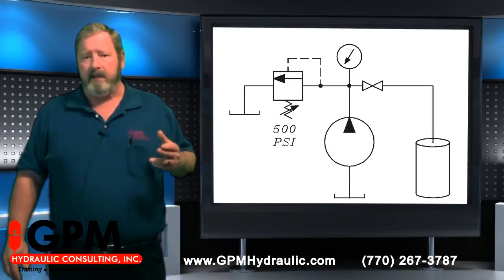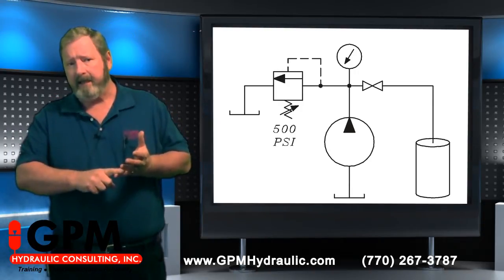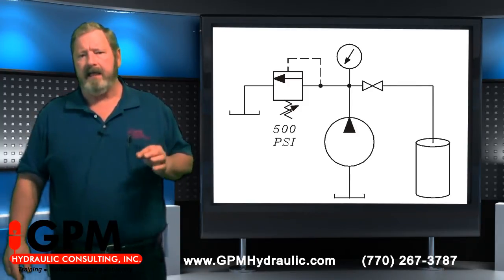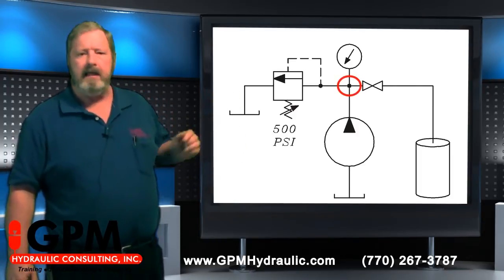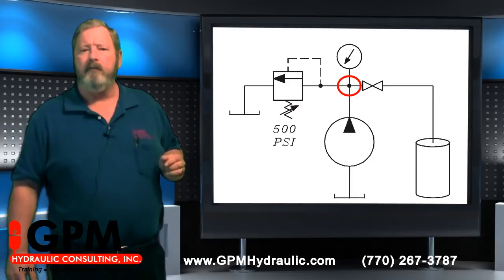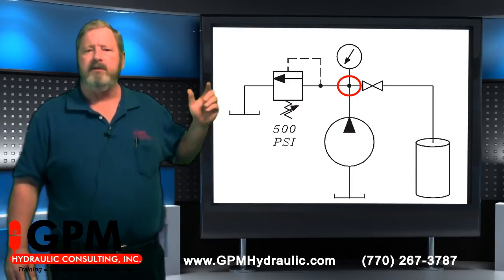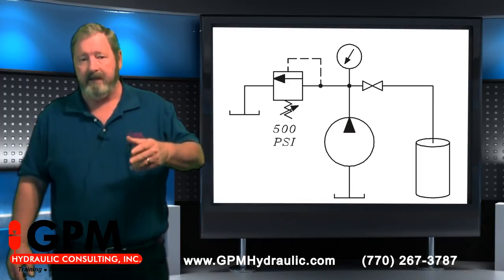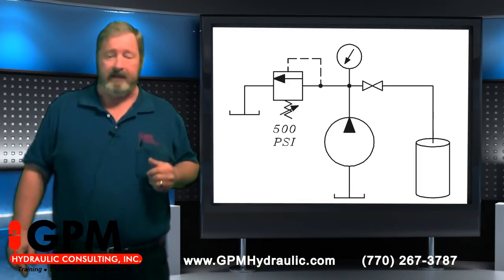Its flow is determined by two factors: its displacement and the speed of the hydraulic motor. Now when we're tracing the hydraulic flow on a schematic and we get to a T in the line, we have to follow both directions to determine the path of least resistance. Hydraulic oil will always take the path of least resistance.